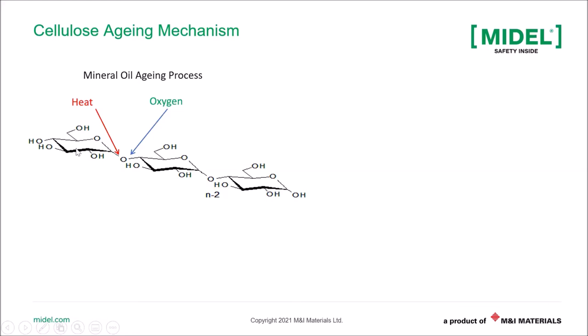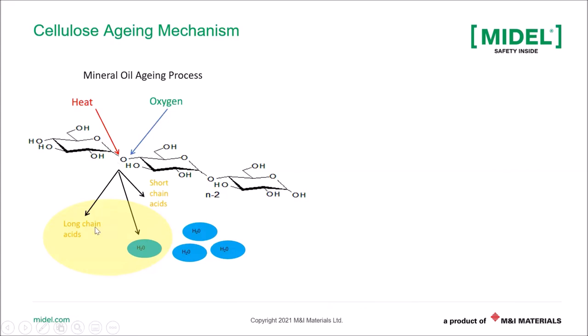So when you think of cellulose material and look at it from a microscopic standpoint, this is what cellulose chains would look like. And in a transformer, you'll typically have heat and oxygen. The heat would be generated when a transformer is energized, from the load loss and no load loss. And you'll have the presence of oxygen as well. So what typically happens is that the heat and oxygen will break down the cellulose chains and create long chain acids and water and short chain acids in mineral oil. Some of the water is held by the mineral oil, depending on what the saturation limit is at the temperature. Now, the short chain acids and the remaining water go in and help break down the cellulose chain further. So this is a continuous aging process that takes place in a transformer.